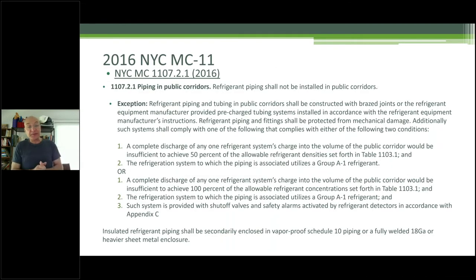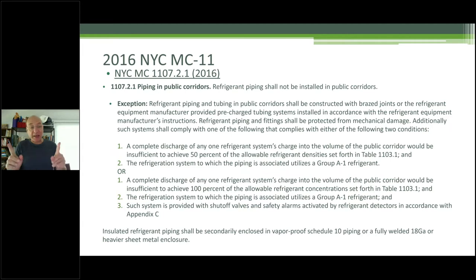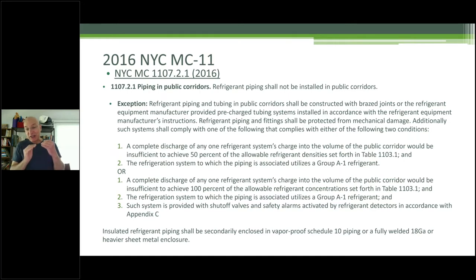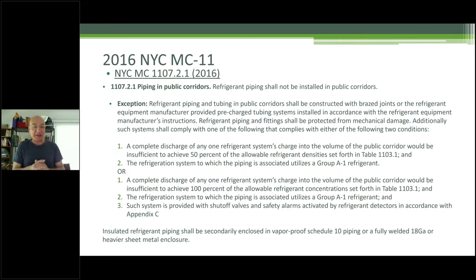What we're moving into: very simply, we kept the first sentence — refrigerant piping shall not be installed in public corridors — except you can install with brazed joints. If you discharge the entire system and don't exceed 50% of the allowable RCL — for 410A that's 26 divided by 2, which is 13 — if your RCL is under 13, you're okay. You can run that refrigerant in the corridor without a fire partition. Of course it has to be above the ceiling and protected. It has to be A1 refrigerant — non-flammable, non-toxic — because that's a means of egress.